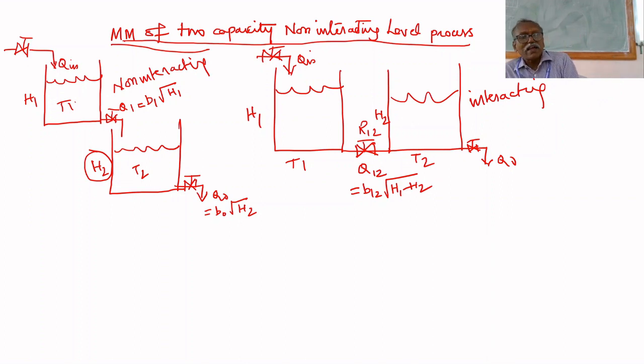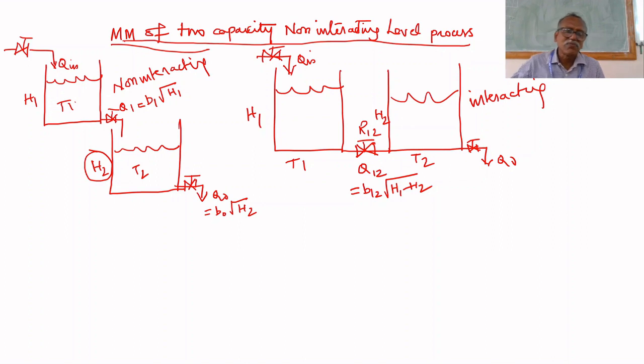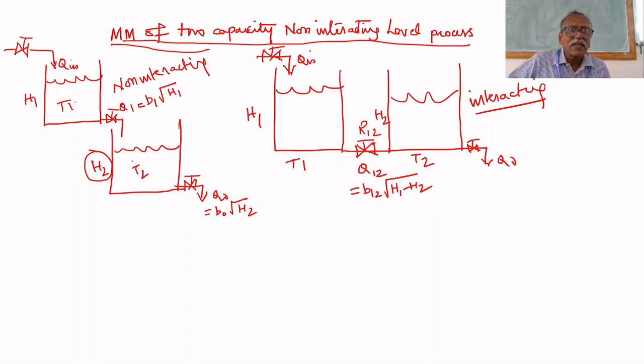The pressure difference across the valve R12 is the pressure difference between tank 1 and tank 2. Therefore, the flow rate from the first tank is a function of the second tank level. So the second tank interacts with the first tank — that is why this is the interacting type of level process. In the non-interacting case, the second tank does not affect the outflow rate of the first tank.